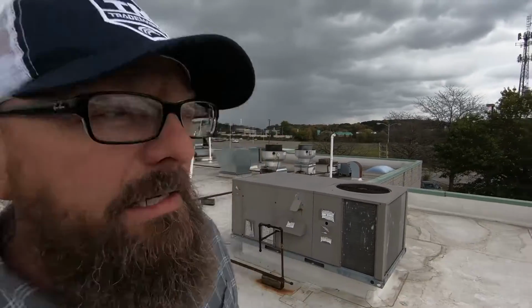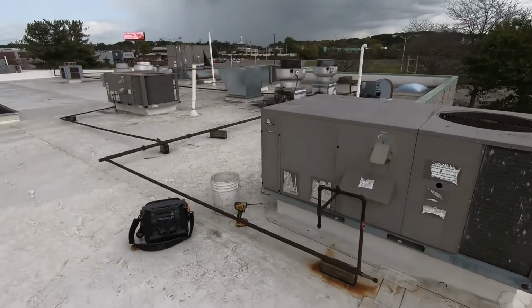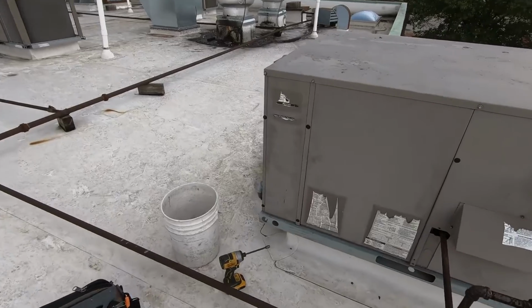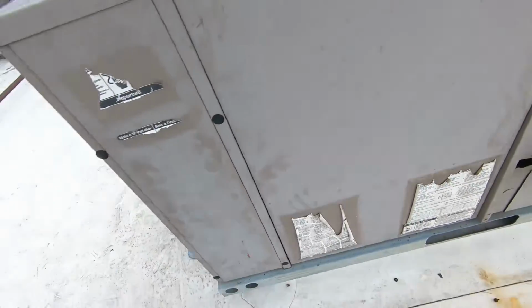First no heat of the season. I went down into the dining room and the thermostat appears to be calling for heat. So we're up here on this little York unit. I'm gonna open it up, see what we've got going on. I hear a blower running, so we should have power. First things first, I'm gonna open up the electrical panel and see if we're even calling for heat.